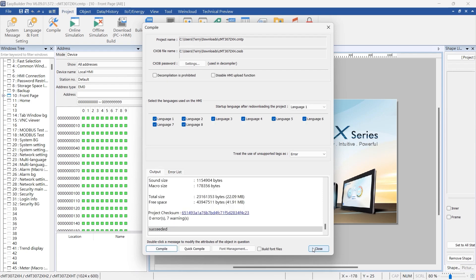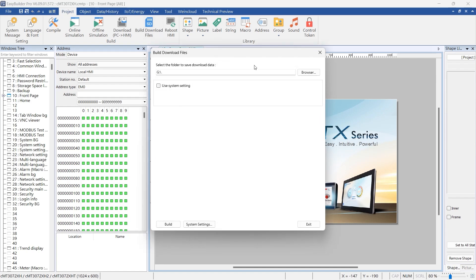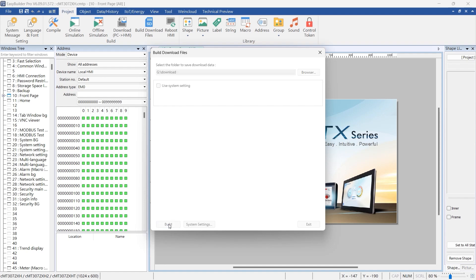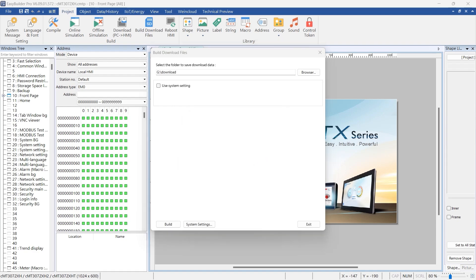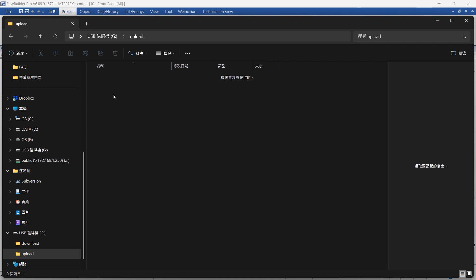With your project compiled, it's time to create the download files. Click Project again and select Build Download Files. This option prepares your project for transfer via external storage devices. A new window will appear, prompting you to choose a directory to save the download file. Browse to the location where you want to store the file and click Build. EasyBuilder Pro will now generate the necessary files. I prepared two folders — one for saving files to download to the HMI, and another for later uploading the project from the HMI.